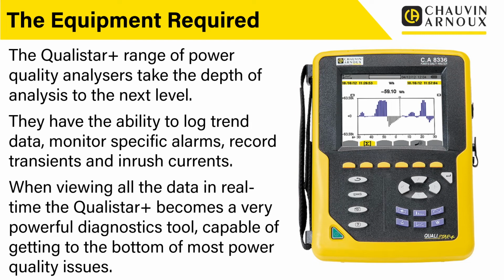We can record transients too - you can set it so if voltage goes over 1,000 volts, it records that transient. It captures the waveform, recording 1 cycle before and 3 cycles afterwards, showing you exactly where that transient occurred, so you can really analyze it.